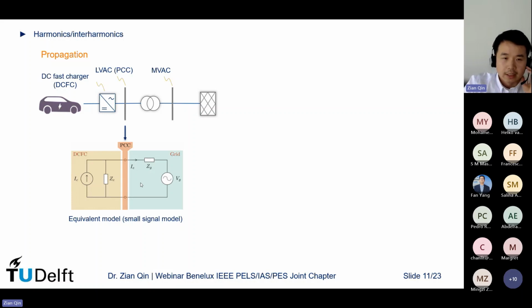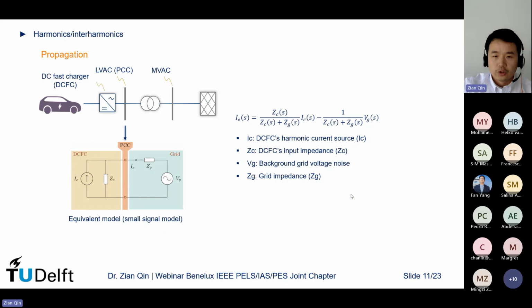But you need to pay attention that here the impedance is not a single value at the fundamental frequency. It's a broadband impedance. And usually you need this impedance value from 0 up to kilohertz to study the harmonic and interharmonic issues. So if you have a circuit model like this, you can calculate the voltage or current at the PCC point. Here I just show an example: the current at the PCC point. It is a function of 4 parameters, right?